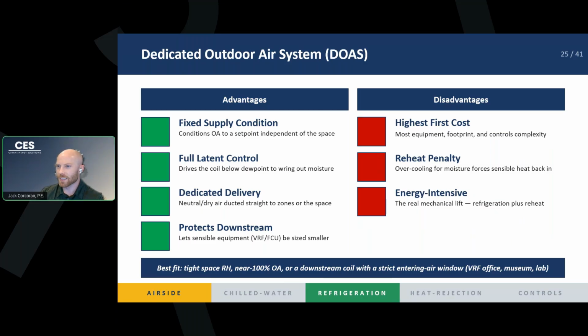That is potentially, that definitely is an energy cost, right? You are reheating the air you just cooled down, right? And that can seem like that's just an energy use that wouldn't be required if you use one of the other systems that just brings it slowly down in steps. This, you overcool it and then reheat it back up. It's less energy efficient. And the last point is you have to use mechanical cooling, which requires energy.